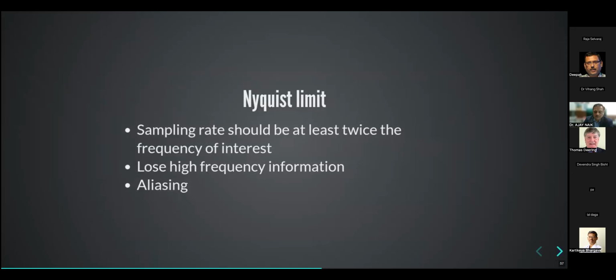Now, the other thing is, of course, you would know about the Nyquist limit and aliasing from echoes. So generally, your sampling rate should be at least twice the frequency of interest. Now, most frequencies of interest for us in an EP lab or in ECG and intracardiac EGMs, most usual signals would be about 100 to 200 hertz. So you would need a sampling rate at least twice this. But there is some other high frequency information, like you might have fractionated signals or His potential. So generally, our sampling rate is around 1000 hertz, so that you can record frequencies up to 500 hertz.